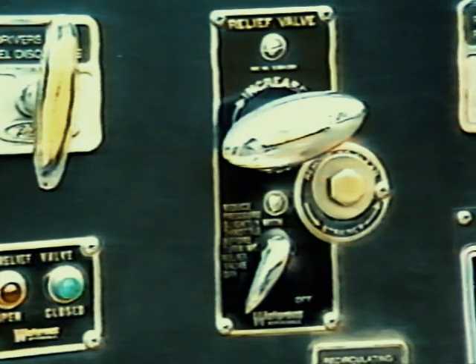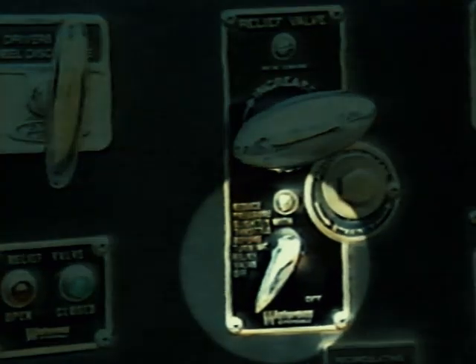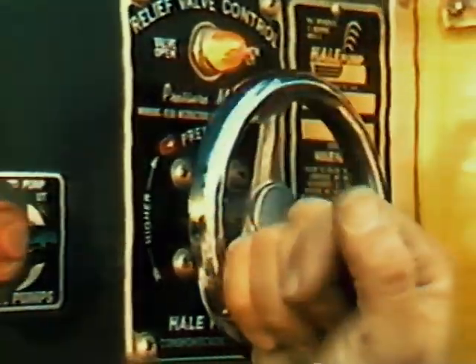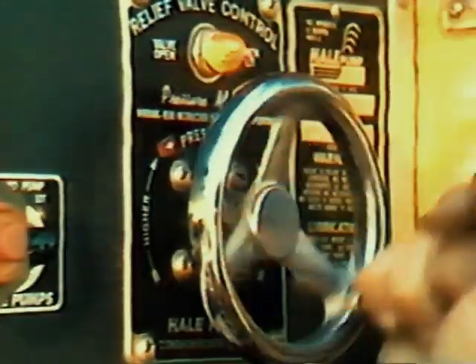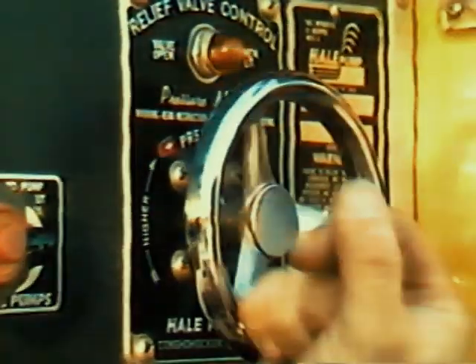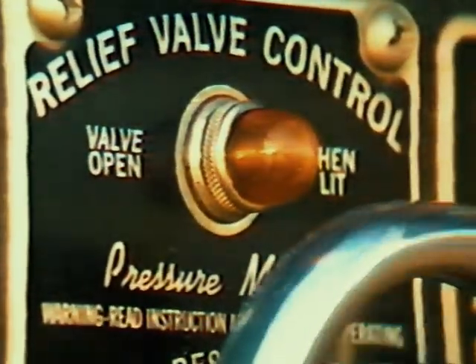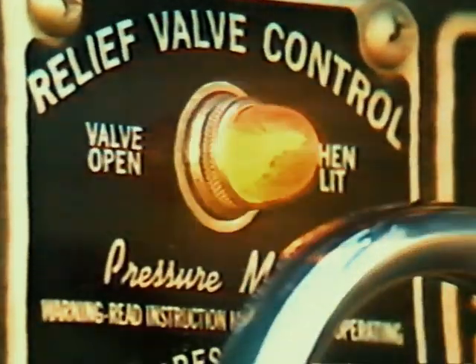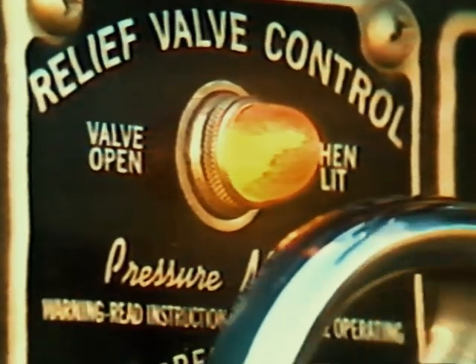The controls for a pressure relief valve usually consist of a four-way valve to place the system on or off, and a control handle or wheel that determines the pressure setting for the relief valve during operation. There may also be a pilot light that comes on when the relief valve opens.